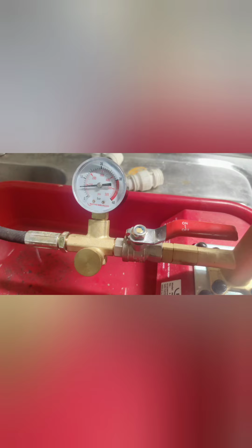Any stop tap used above or below ground must be made from either gunmetal or corrosion-resistant brass to prevent dezincification of the stop tap. The water regulations state every water fitting shall be immune to or protected from corrosion by galvanic action or any other process which is likely to result in contamination or waste of water. Source: Schedule 2, Regulation 3.